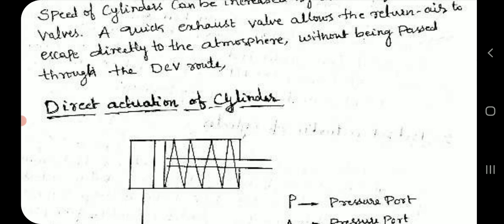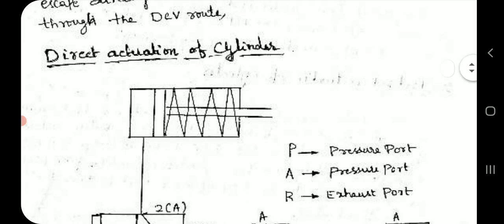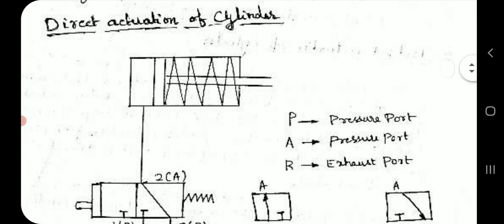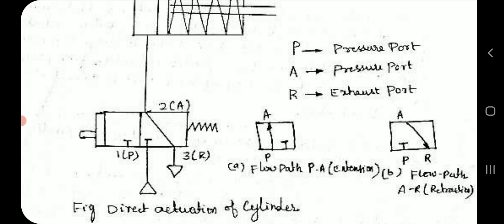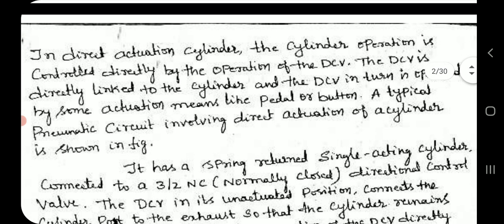In direct actuation of a cylinder, the pressure port is P, the actuator port is A, and the exhaust port is R. The extension flow path is P to A, and the retraction flow path is A to R.